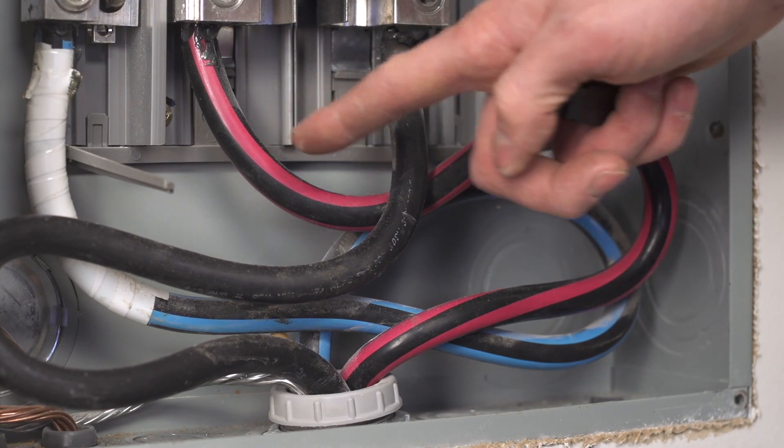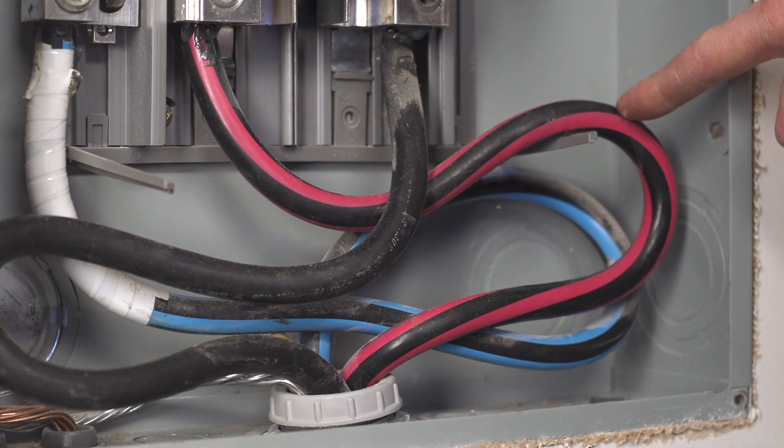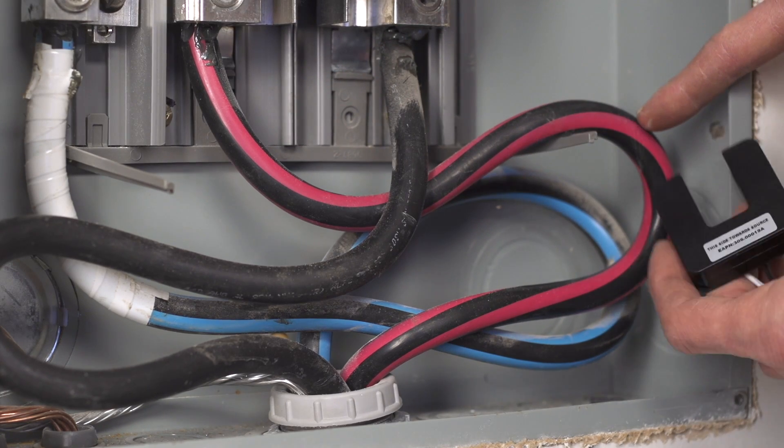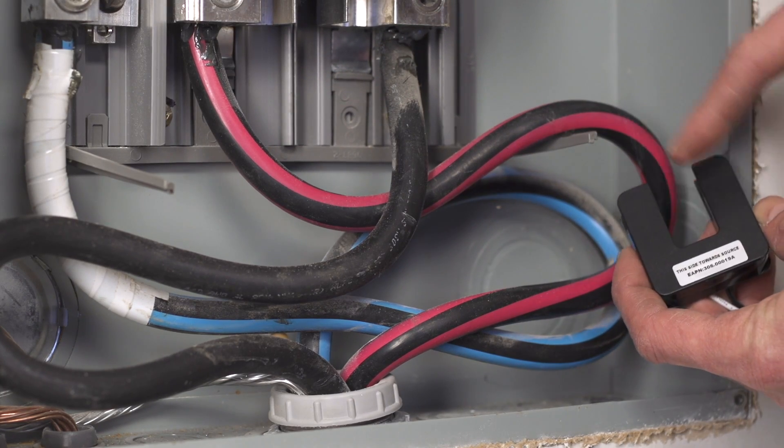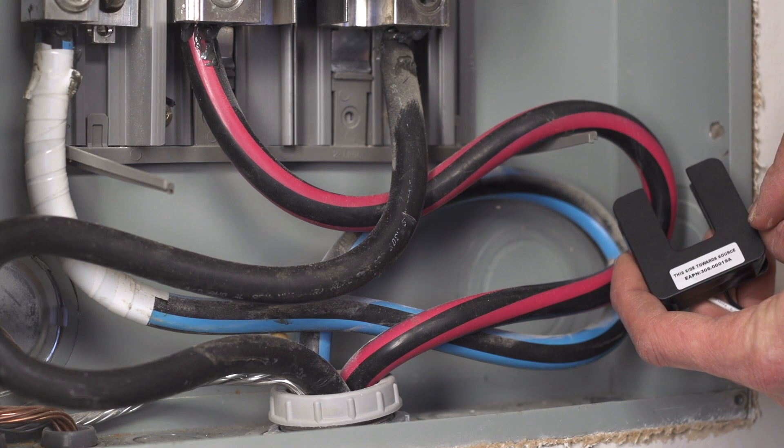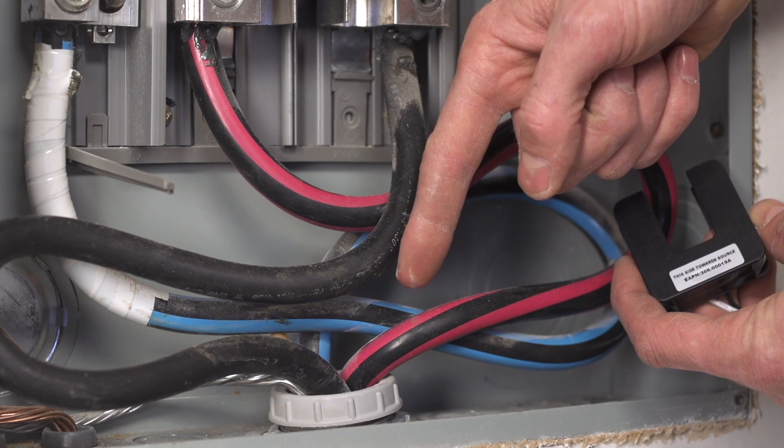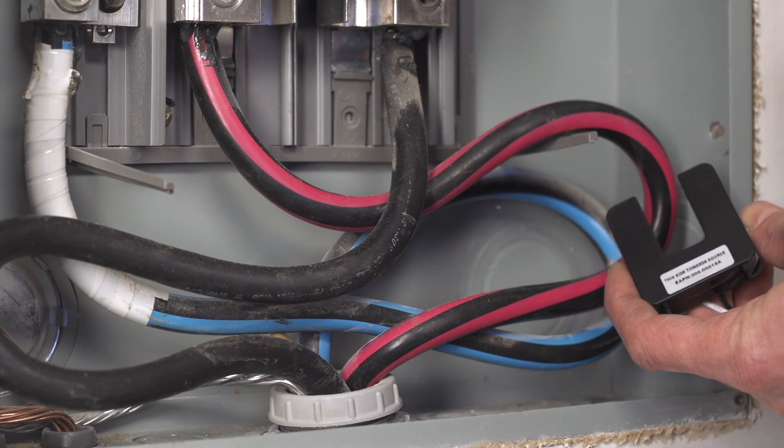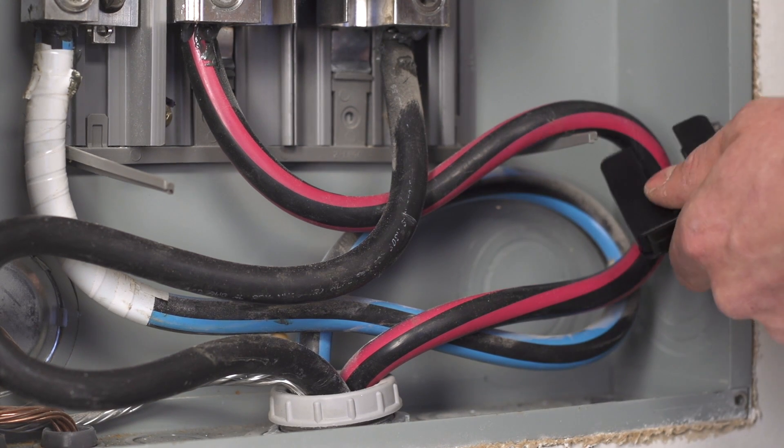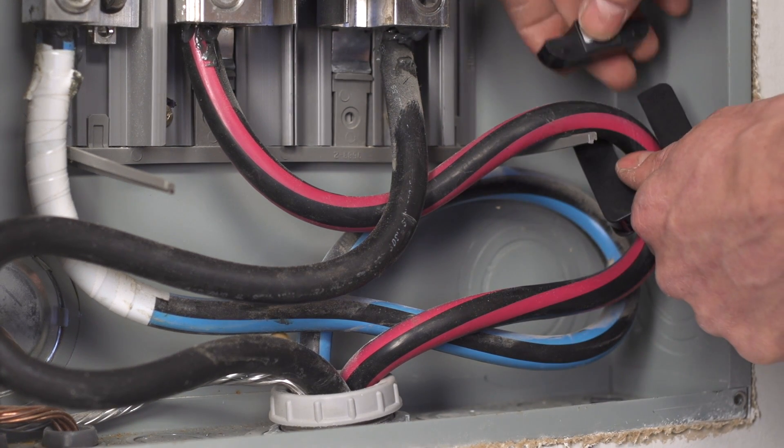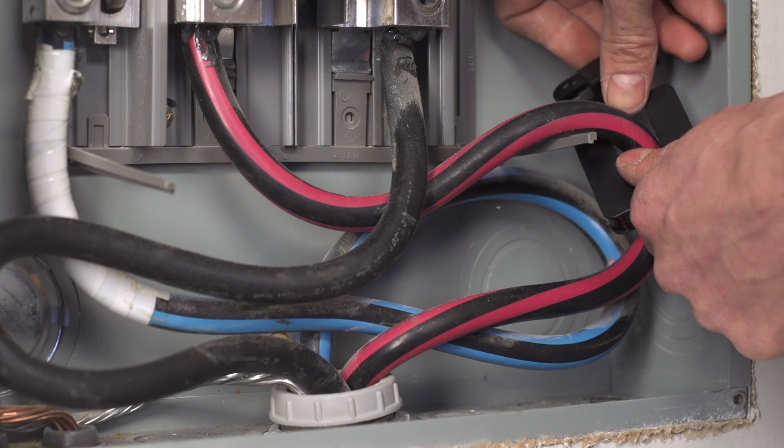Then loop one CT around one of the main lines, making sure the sticker on the CT faces towards the direction of where the power is coming from and not the breaker panel. Then replace the bracket.